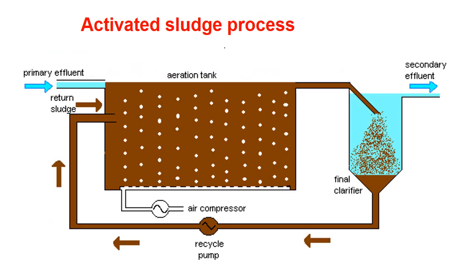Here we can see an example with a diagram of the biological process — this is the aerobic activated sludge process. Sludge is the solid part coming out after treatment and will contain the bacteria. That sludge is used like a culture and added with the incoming effluent. When in the presence of air and given sufficient time, these microorganisms grow and digest all the solid materials present. That is the activated sludge process.